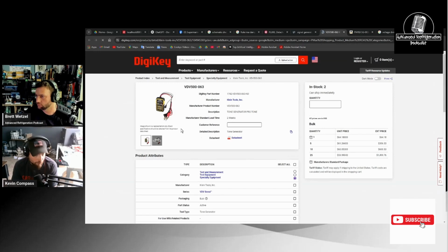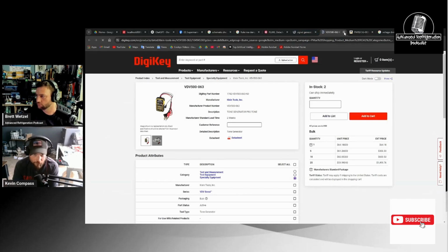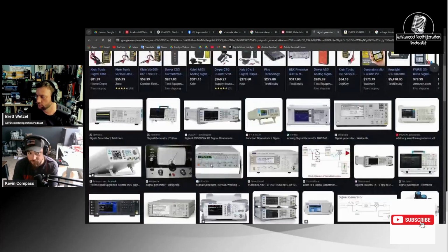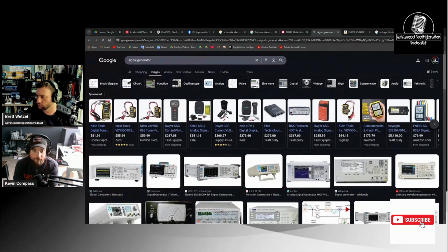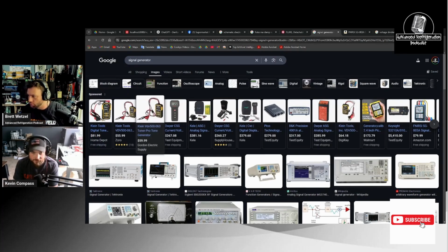And same thing, you could also have outputs of 4 to 20 milliamps. So just like an input, you could also output another device 4 to 20 milliamps. And it's going to be checked the same exact way. You wire your meter in series with that device that you're sending 4 to 20 milliamps out of. So generally, I think Microthermal could do 4 to 20 milliamp outputs. I know RDM does. A lot of our stuff is going to be DC only.